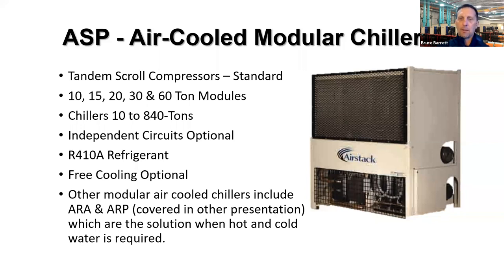That free cooling option is optional. It comes in its own module. It looks almost identical to a mechanical module with compressors. Again, it's a water coil versus refrigerant coil. We do have other modular chillers, and I'll talk about the ARA at the end. We did touch upon that ARA chiller during the electrification seminar last week.